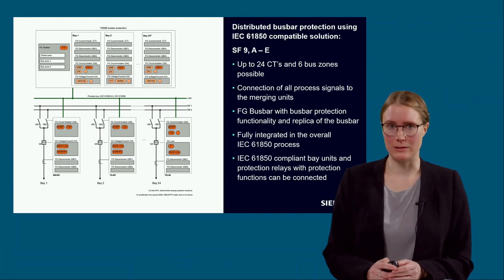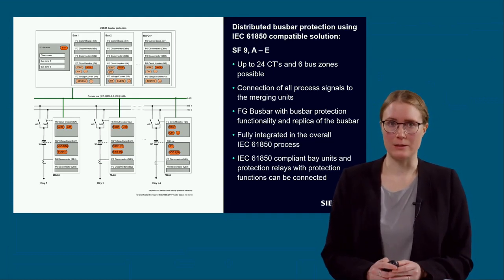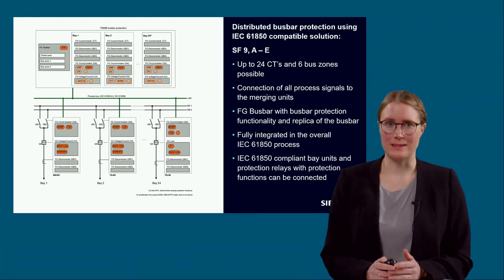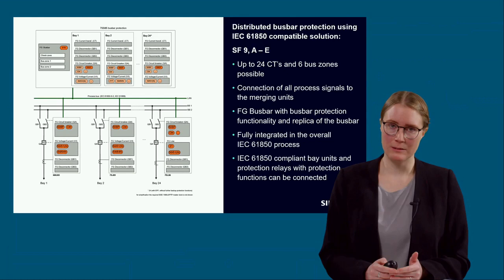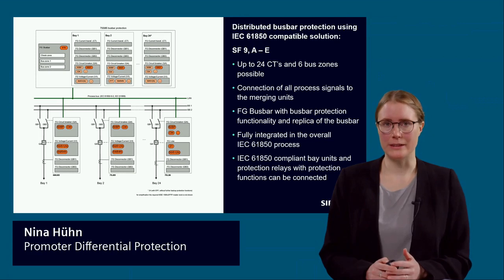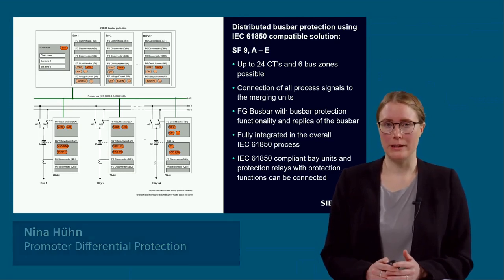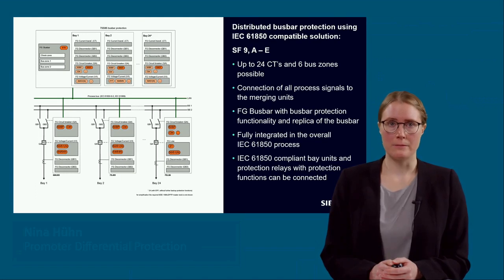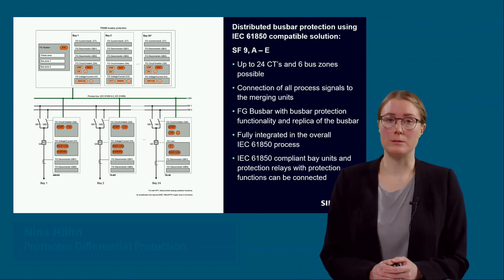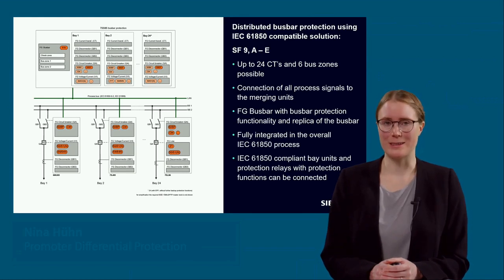61850 communication configuration in the system configurator for this solution. A description of these necessary steps can be found in the manual, but a good understanding of process bus is required in this case. The engineering effort is significantly higher compared to the centralized approach. With the solution, up to 24 CTs and 6 bus zones are possible for a distributed setup. The 7SS85 is fully integrated in the overall IEC 61850 process, and it is possible to integrate IEC 61850 compliant merging units from other vendors.